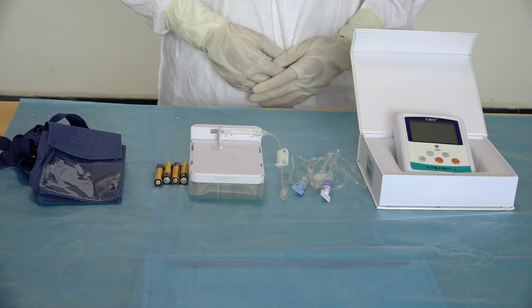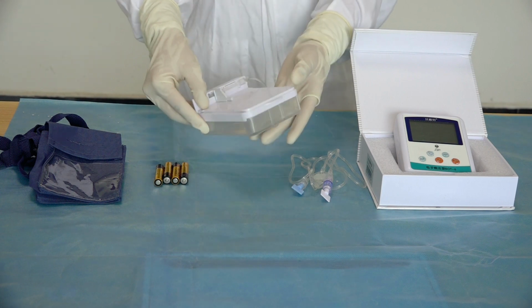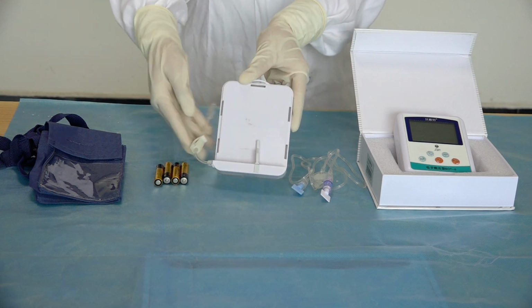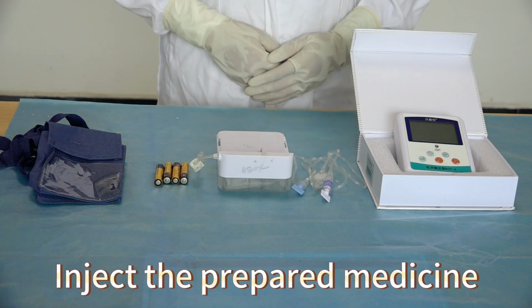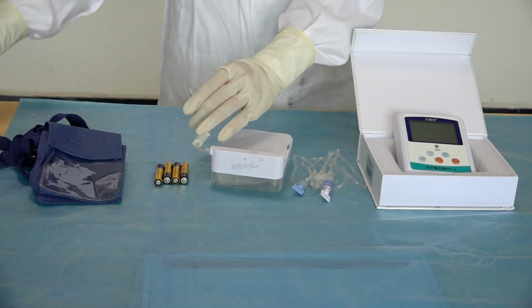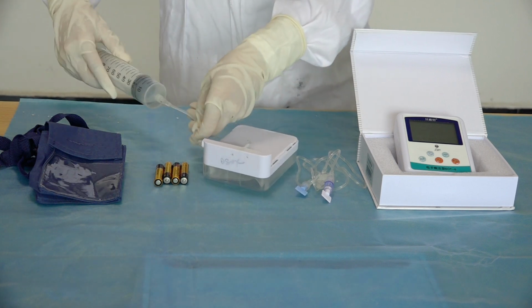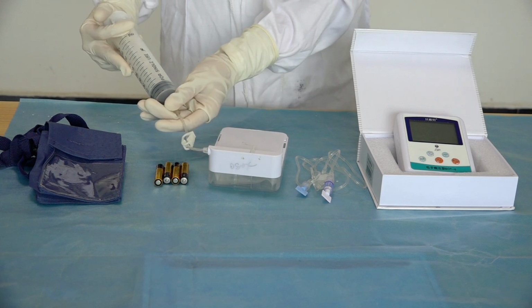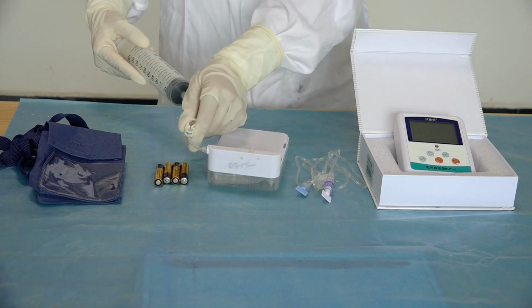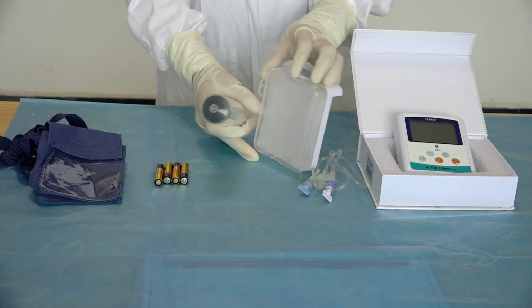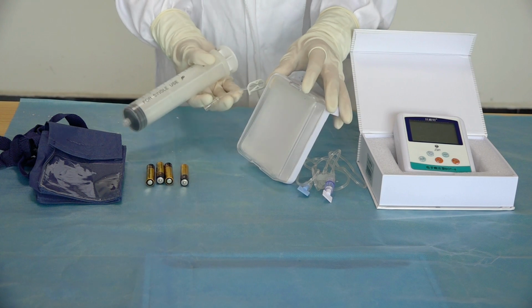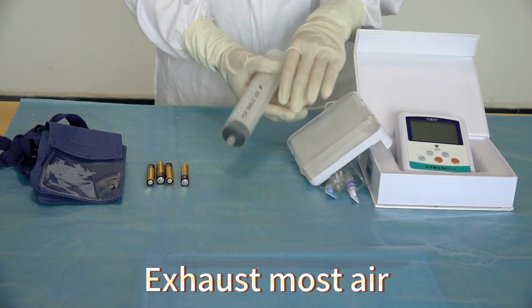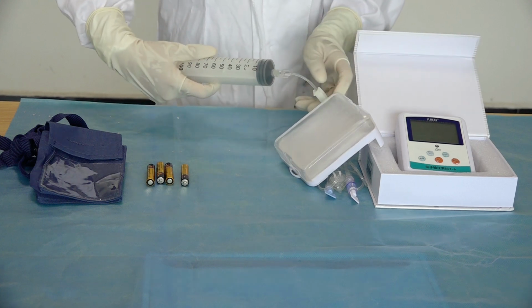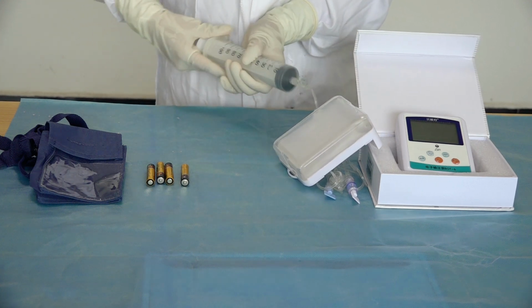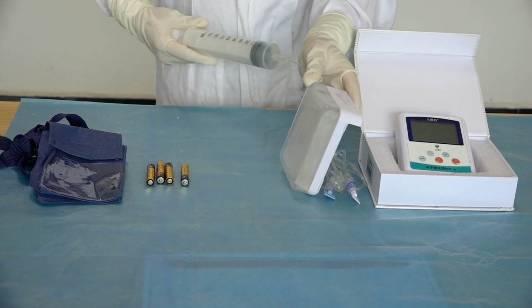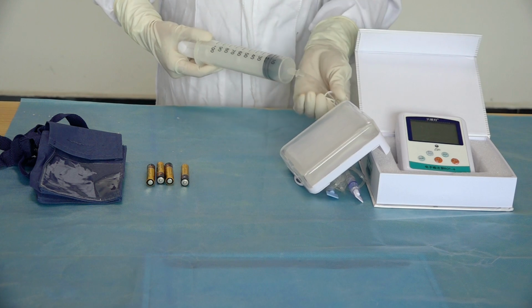Step 1. Unpack the liquid storage component, take out the medicine box and accessories, do not pull out the white key. Then inject the prepared medicine into the filling port. After the injection is completed, place the medicine box in the direction of the arrow marked on the medicine box. Use a syringe to exhaust most air inside the medicine bag, and clamp the clip after the air bubbles are exhausted and connected to the port of infusion pipeline, which is far from the unilateral valve.